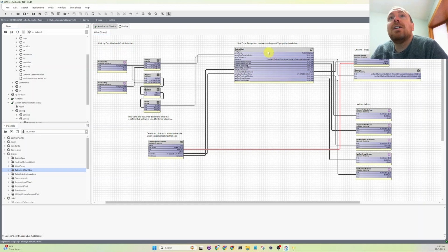There's code inside here, a mathematical model. It'll use these degrees per minute to try and recover the zone, to calculate how many minutes it'll take to recover the zone, and it'll continuously tune these numbers. Then there's an output block that can be trended for the last run predicted minutes, and also last run actual minutes, because there'll always be a little bit of error, and also last run minutes error, which is basically the difference between these two. So this is something that should tune itself and get better and better over time.